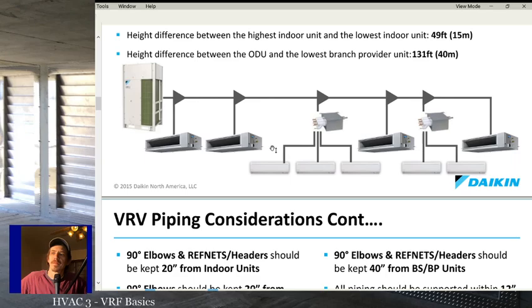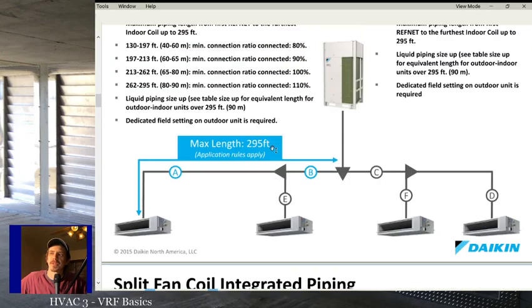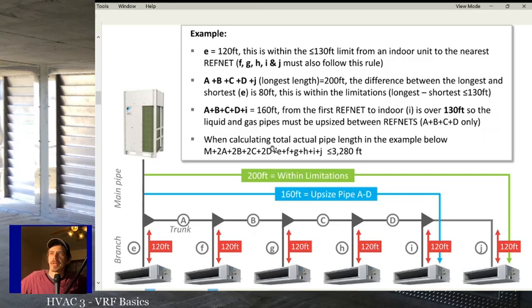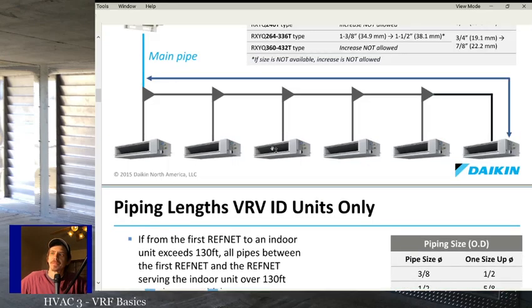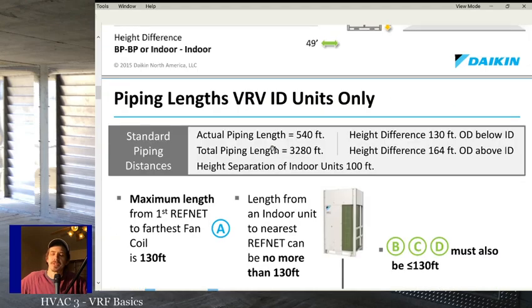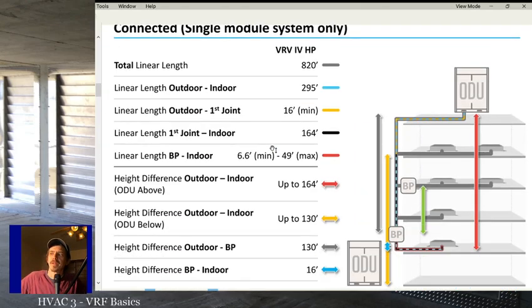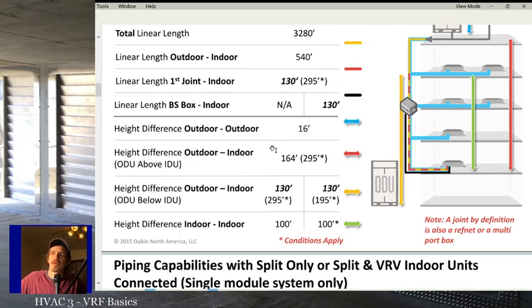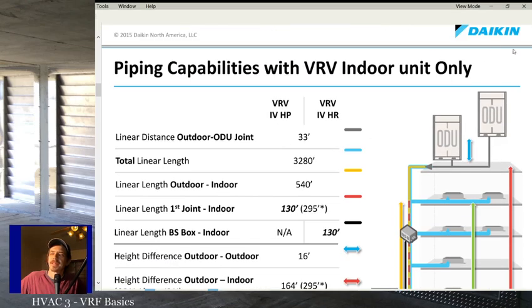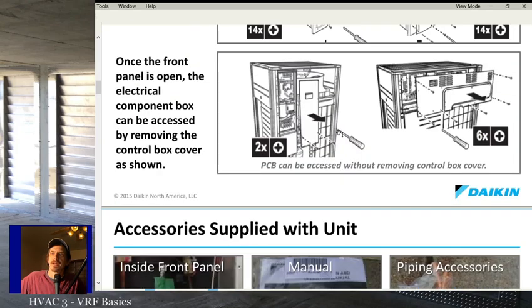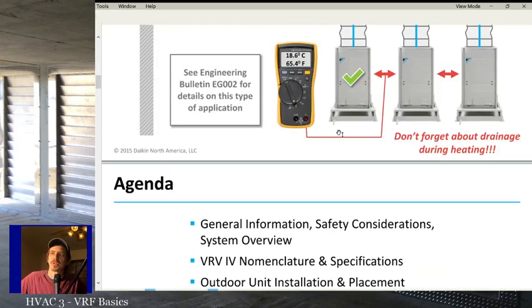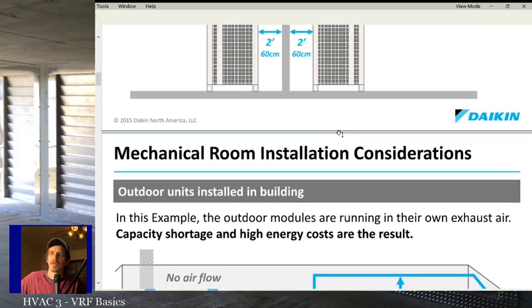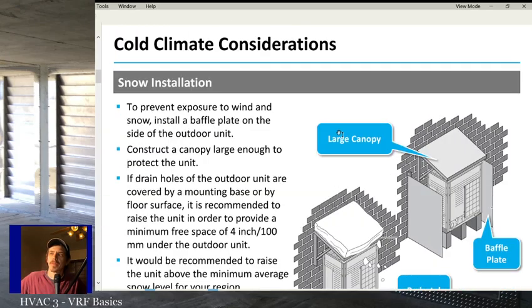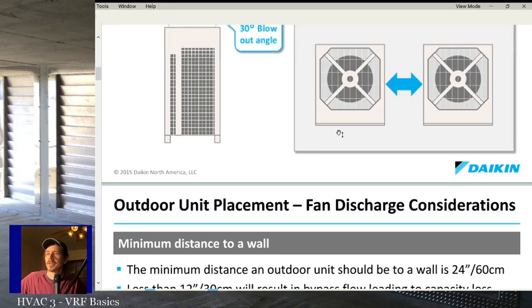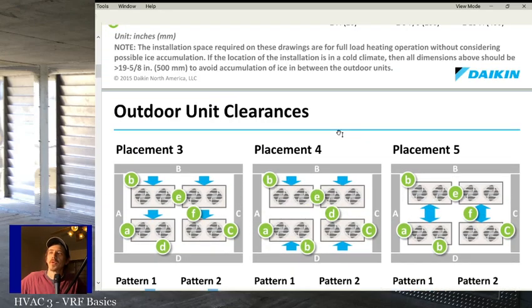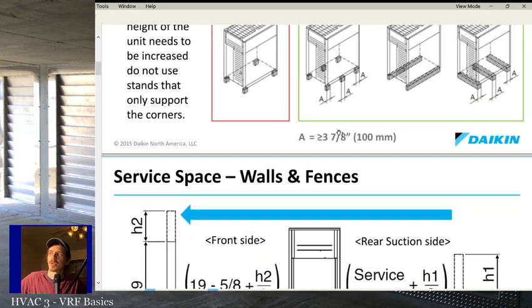Now, the thing about VRF, especially heat recovery, other than that, is as you guys see me flipping through all these pages, there's a lot of installation instructions. This is the other thing that's common between mini splits and VRF, and that is the fact that you really need to understand the manufacturer's instructions when installing the equipment. It is critical that when you are installing this equipment, VRF and mini splits really, that you are familiar with the manufacturer's requirements for the installation.